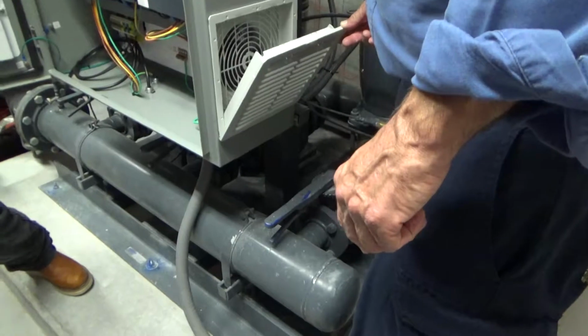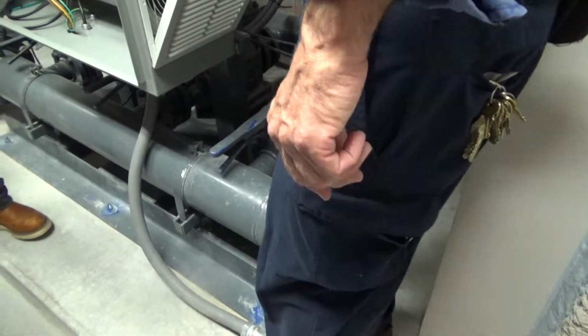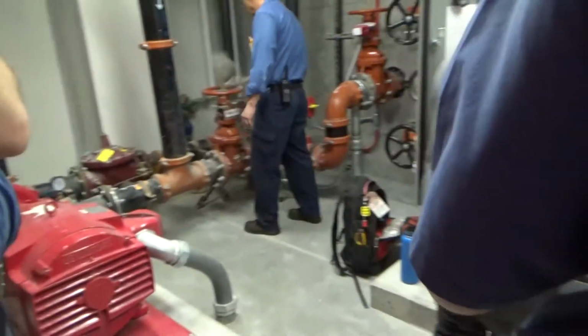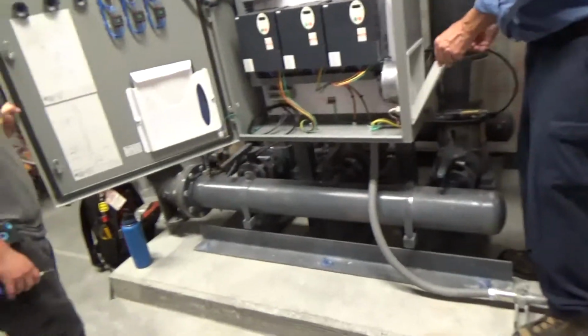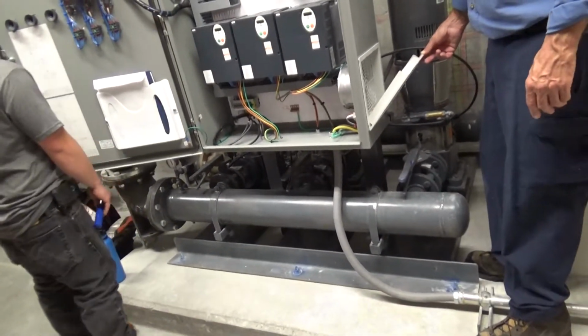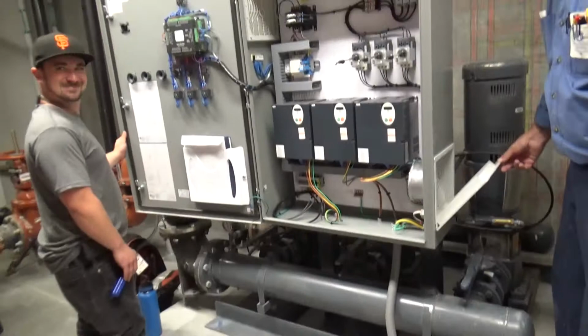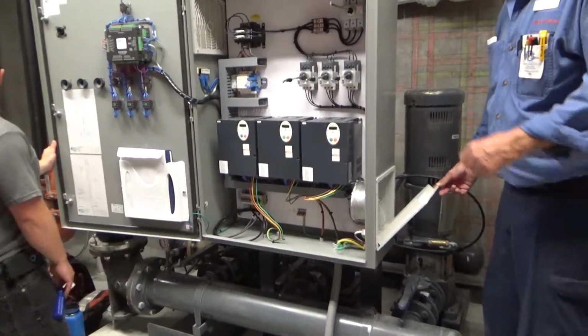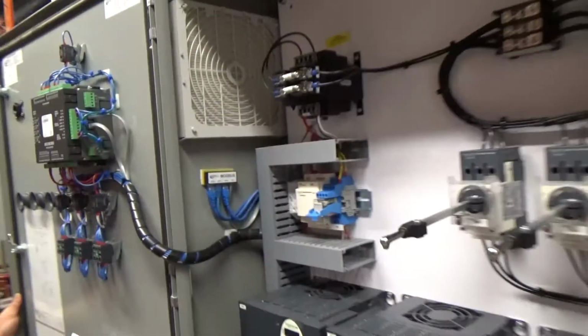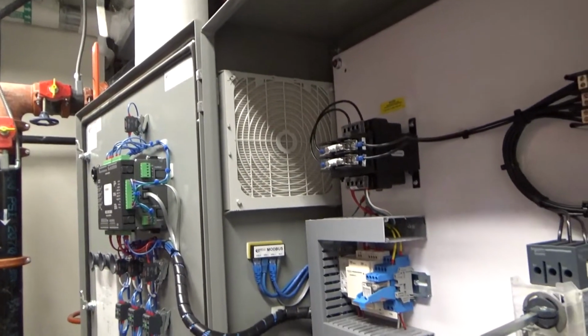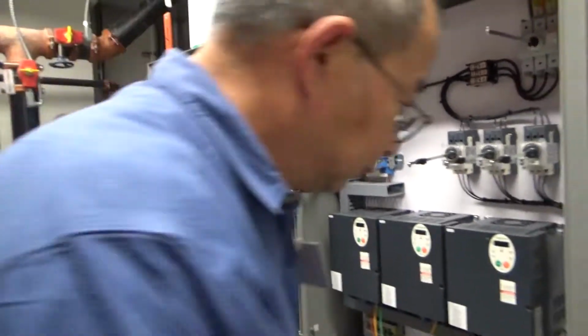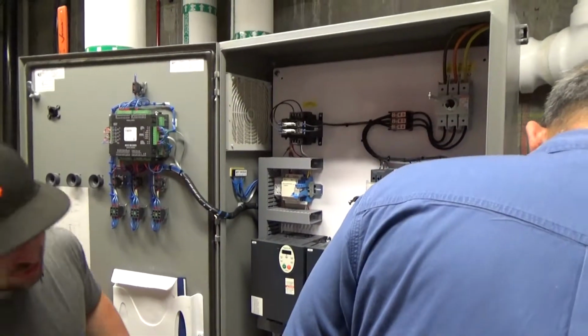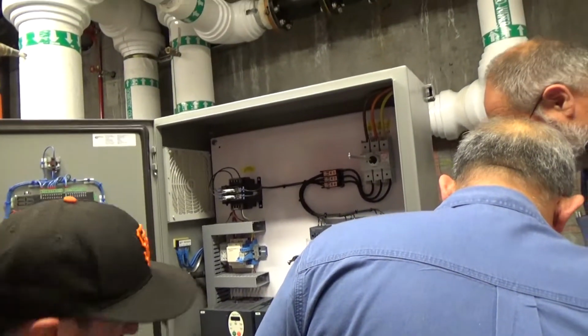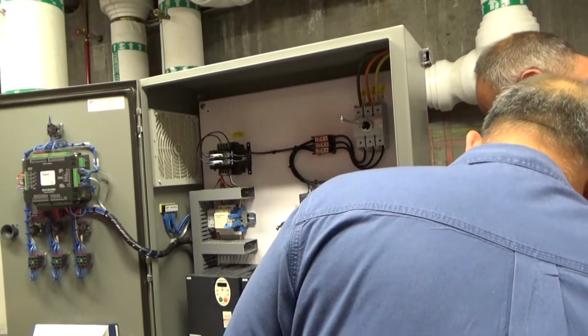So I'm glad we pulled that out. Now we know that it probably should be changed. Ooh, man, that's a good one. Wow, the damn construction dust gets you every time. Now you got something to do, Richard. You come in and clean all the dust off the pump line. Looks like there's a filter right there too. It's dirty, you know. They've already cleaned this room though. Well, they gotta do it again. Did you check your flow direction? Alright, there you go. Very good.